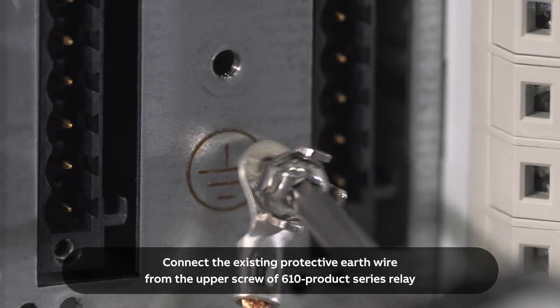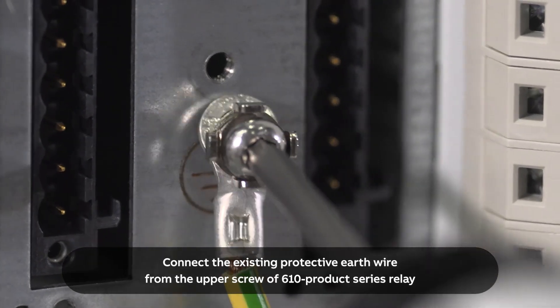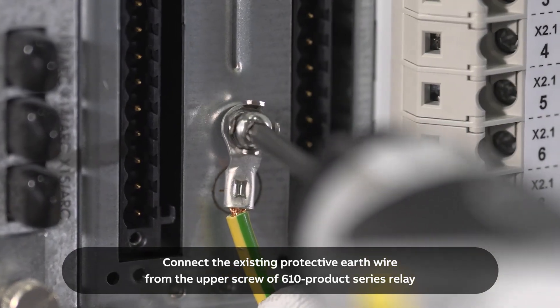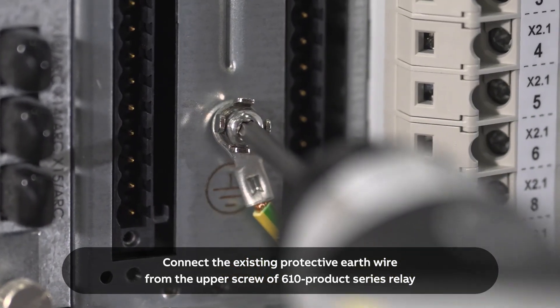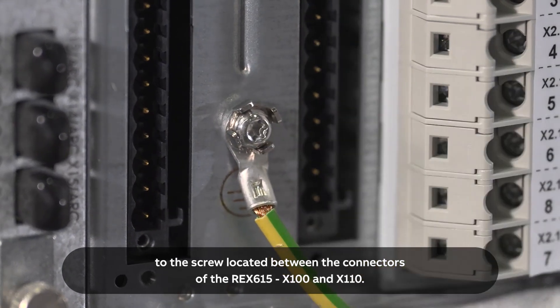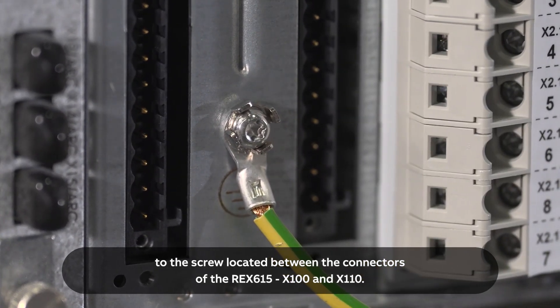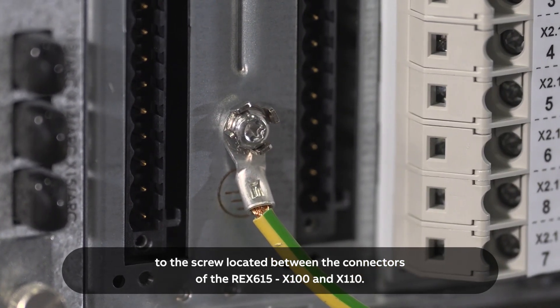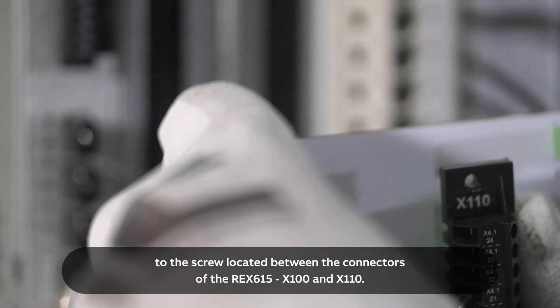Connect the existing protective earth wire from the upper screw of 610 product series relay to the screw located between the connectors of the REX615, X100, and X110.